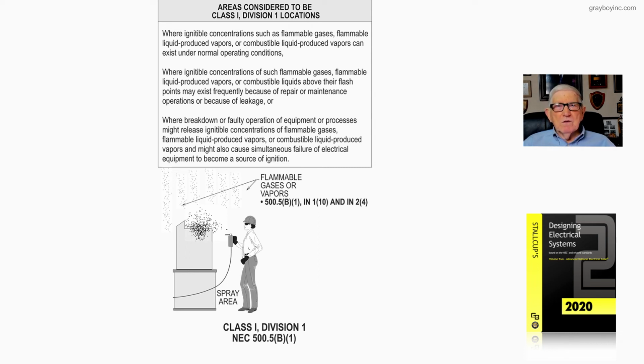And for your seals, if you needed those, you would go to 501.15(A). And then, of course, after you've selected your equipment, you'd go to 501 and see if the equipment you selected fell in that grouping of equipment that's listed in Article 501. And basically, that is exactly what this figure 21-8A is illustrating to the designer and the installer of classified areas where they're installing their equipment.